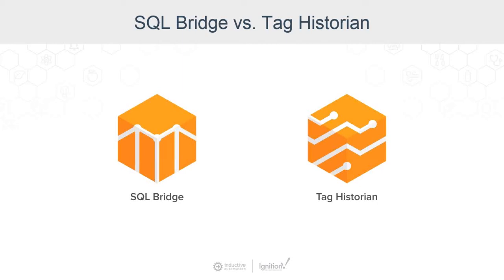By comparison, the SQL Bridge module is what we like to call a transaction manager. It is a way of moving data between an OPC server or PLC and a SQL database. We can move data any way that we want — either on a schedule, on a timer, or on triggers. There is really a big difference between these two modules: SQL Bridge can perform a lot of functionality, whereas Tag Historian is focused on trending and being easy to use.